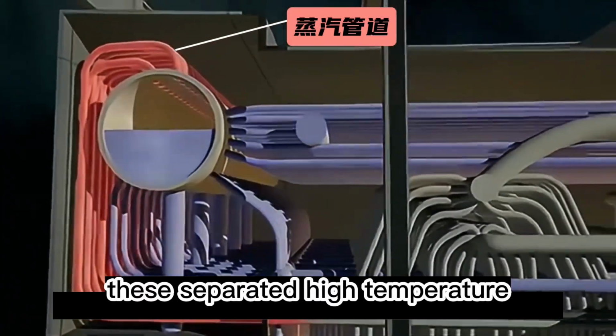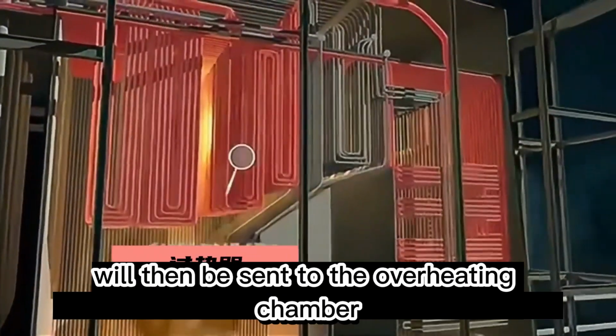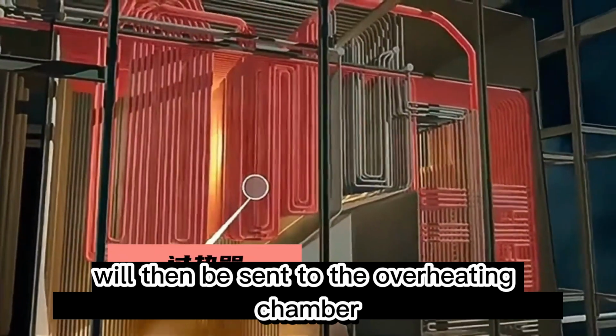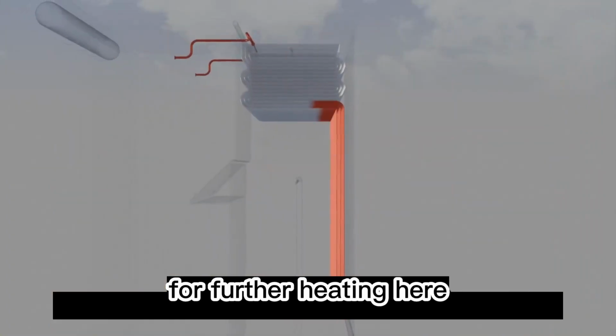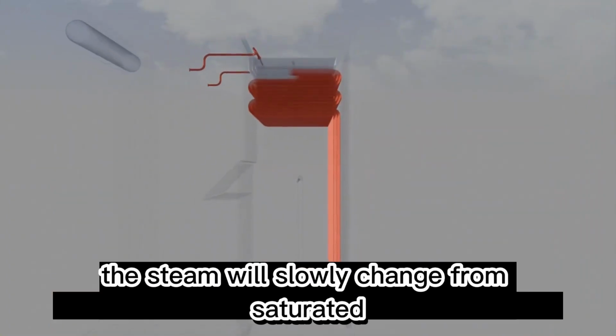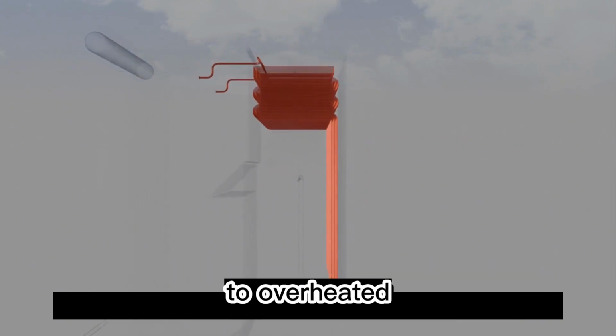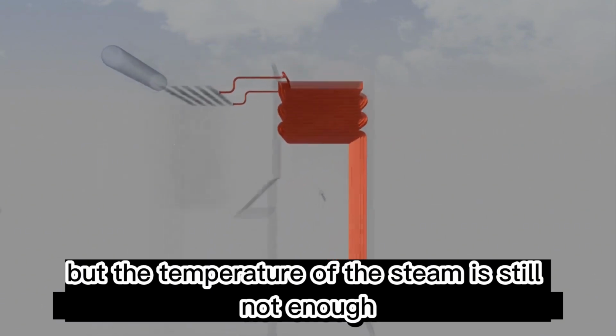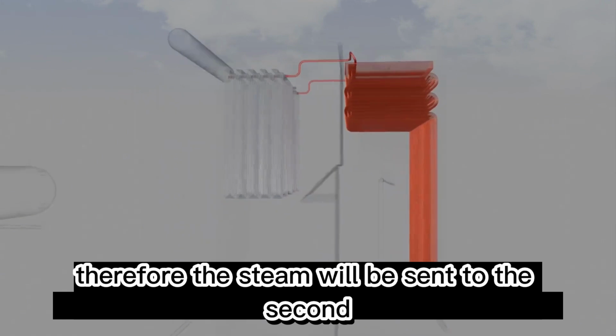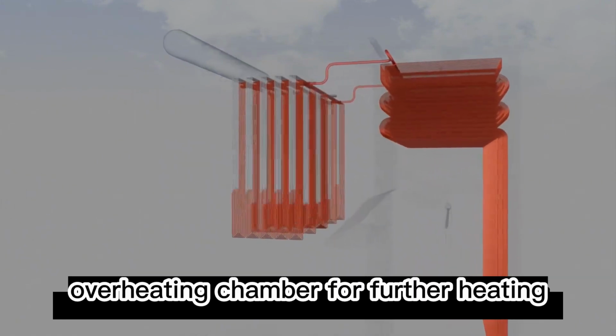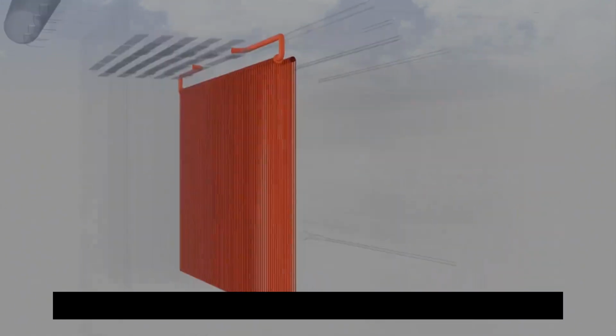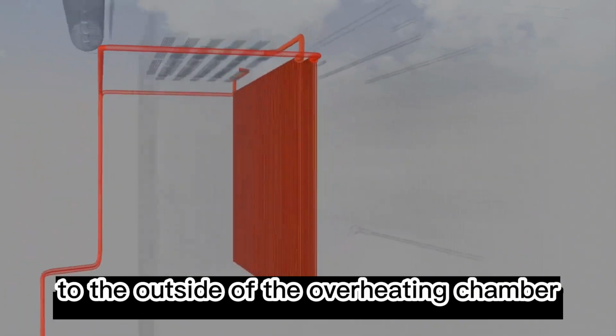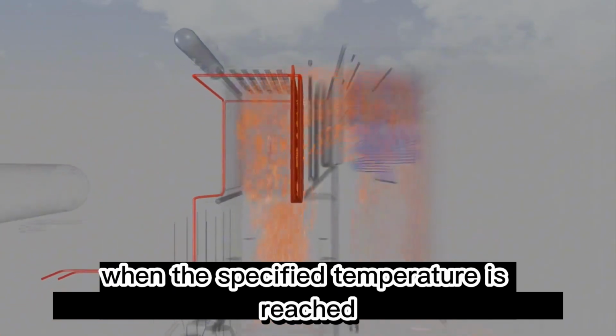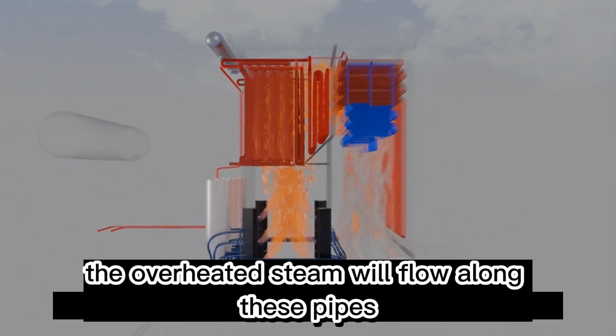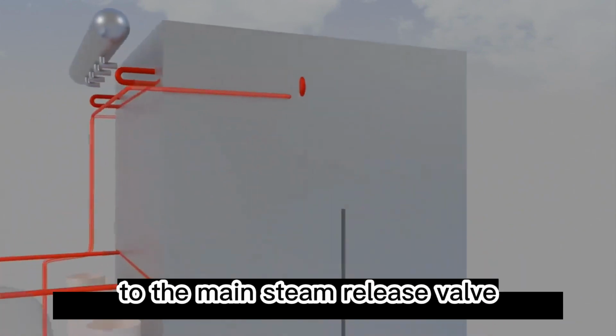These separated high-temperature, high-pressure steam will then be sent to the superheating chamber for further heating. Here, the steam will slowly change from saturated to superheated, but the temperature of the steam is still not enough. Therefore, the steam will be sent to the second superheating chamber for further heating. There are several pipes to the outside of the superheating chamber.